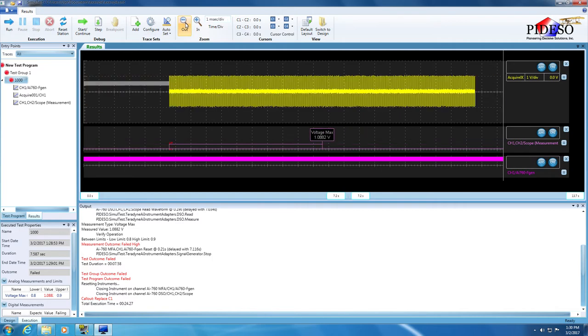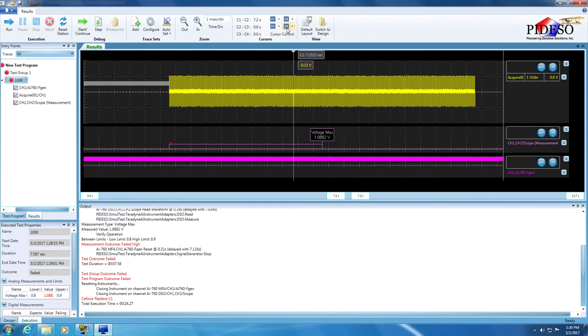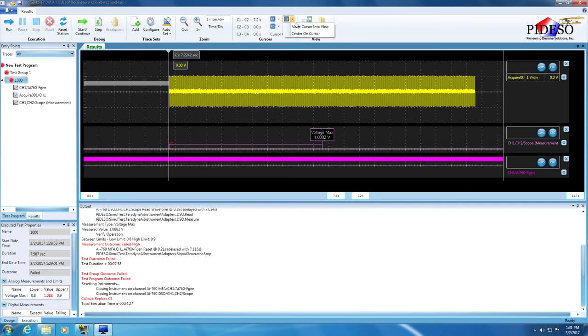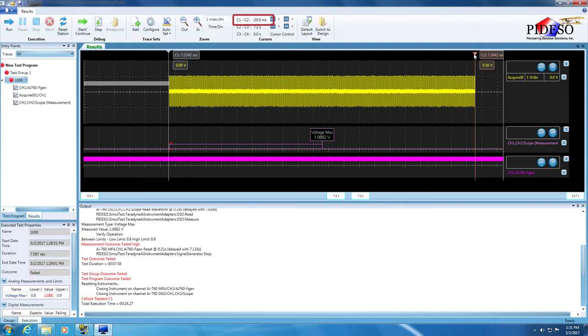You can use the cursors provided by Simultest to mark up to four positions of interest within the signal display and also to make time measurements. Let's bring cursor C1 into view. Go to the cursor's toolbar group and click on the C1 arrow to show the available options. Select Move cursor into view. This will draw the C1 cursor on the results area. Its position represents the elapsed time since beginning of a test in the continuous time domain. Drag the cursor by clicking on the upper arrow and align it with the start of the acquired signal to see the exact time where the acquisition operation started. Bring the C2 cursor into view and move it to the end of the acquired signal. The C1-C2 entry in the toolbar will display the time elapsed between the positions of the two cursors. In this case it will match the duration of the acquisition operation as we have configured it in the channel diagram.